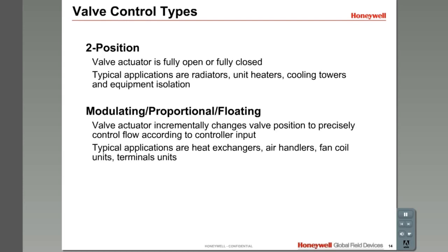Floating control is a type of modulation based on timing. An electric motor is driven clockwise or counterclockwise for a specific amount of time to reach the desired position.